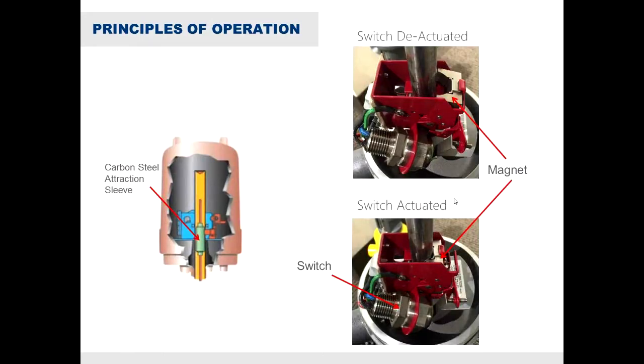The switching element inside the housing works like this: the attraction sleeve has carbon steel or magnetic material inside it, sitting inside the enclosing tube within the process. On the outside, you have the actual switching mechanism with a magnet that sits on the outside of the enclosing tube. When deactuated, that magnet is away from the tube. When actuated, the attraction sleeve goes up into the enclosing tube and interacts with that magnet, pulling it towards the enclosing tube to actuate a micro switch inside the housing.